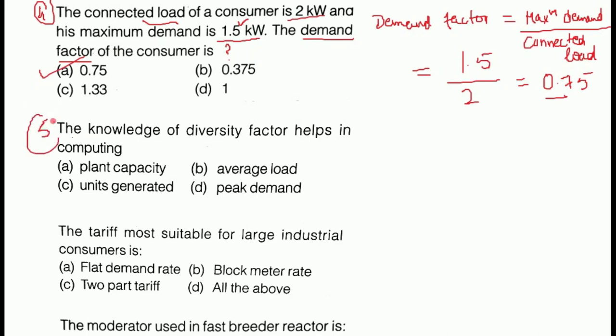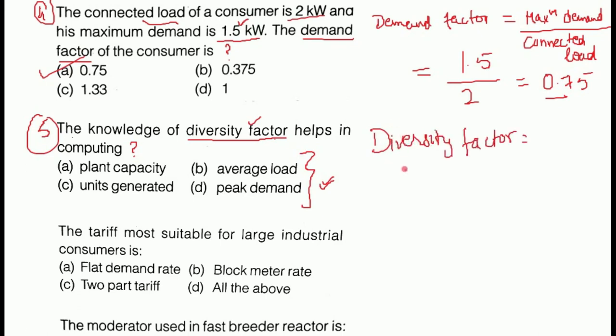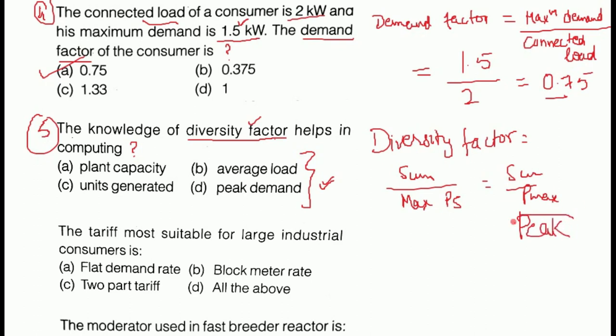Next is question number 5. The knowledge of diversity factor helps in computing what? As you know, diversity factor equals the sum of individual maximum demands divided by the maximum demand of the power station — also called the peak demand. Maximum demand and peak demand are the same. If you know the diversity factor and individual maximum demands, you can calculate the peak demand. Therefore option D is the correct answer.